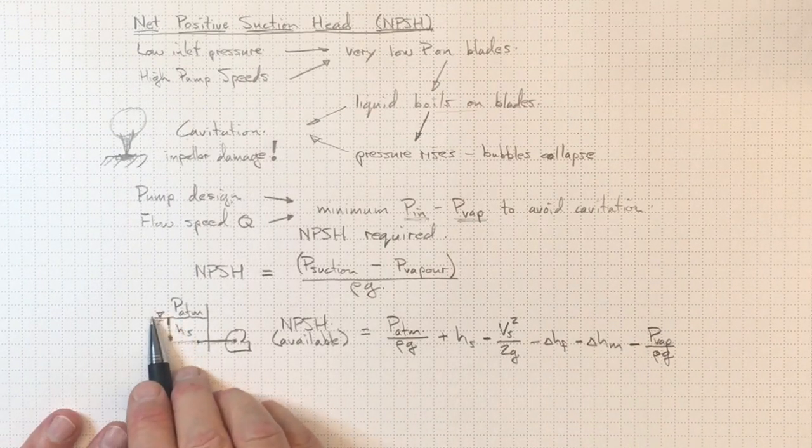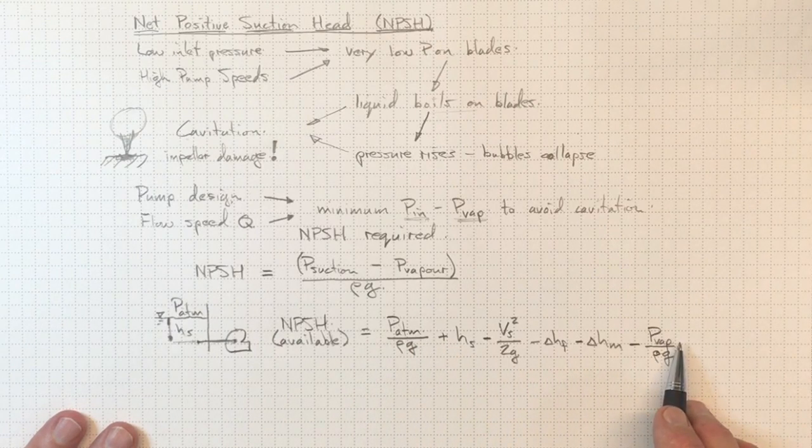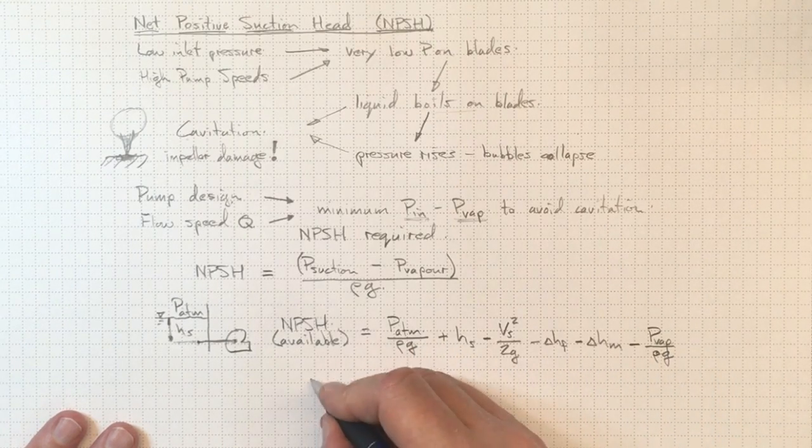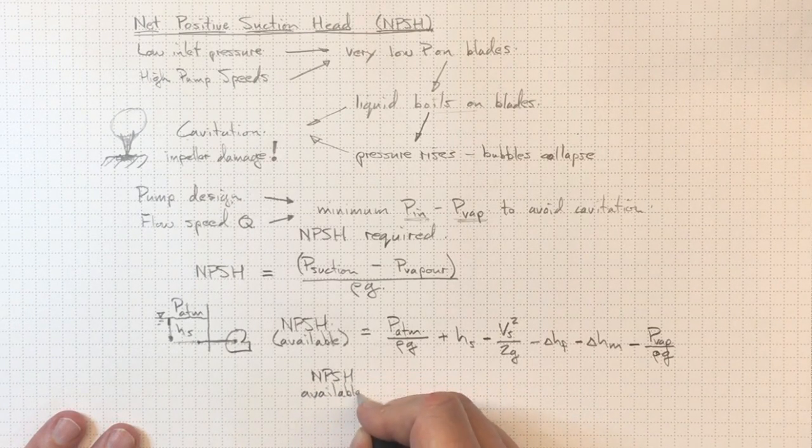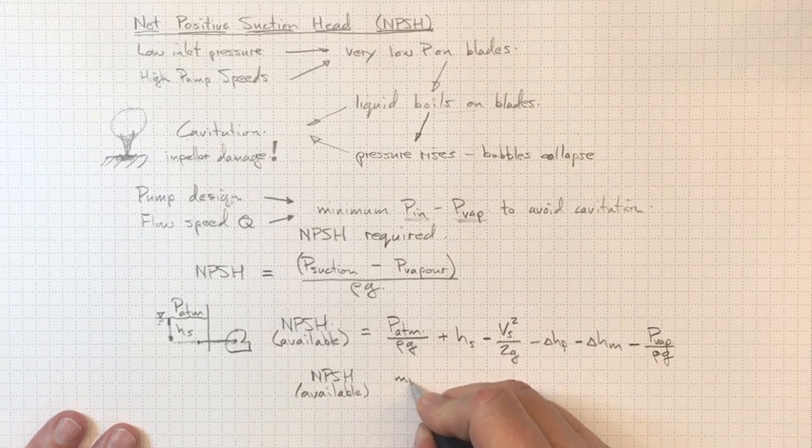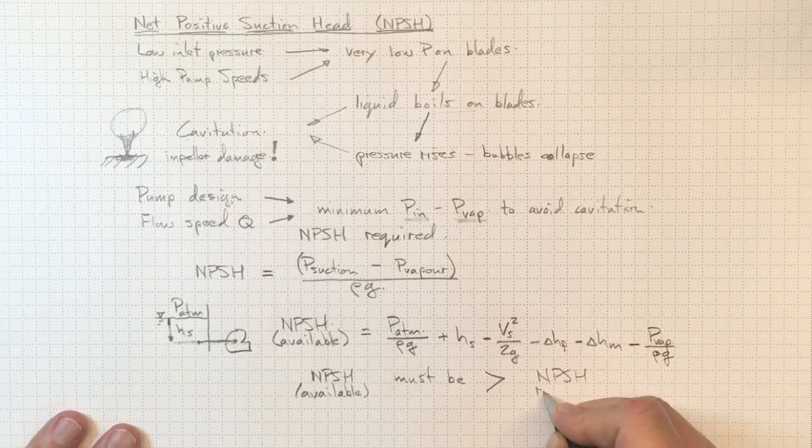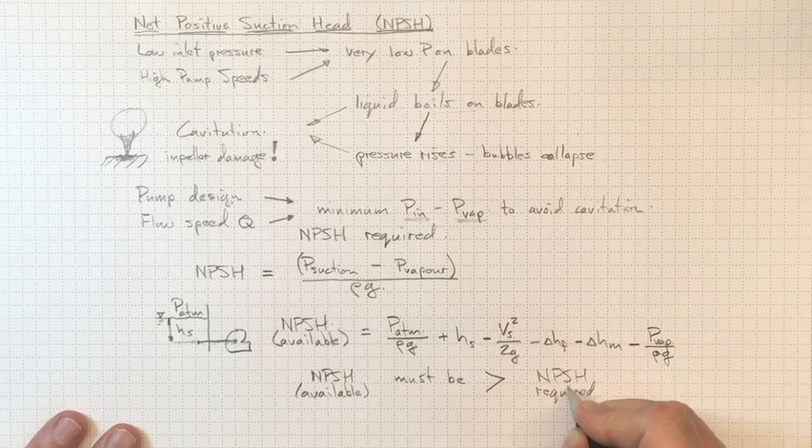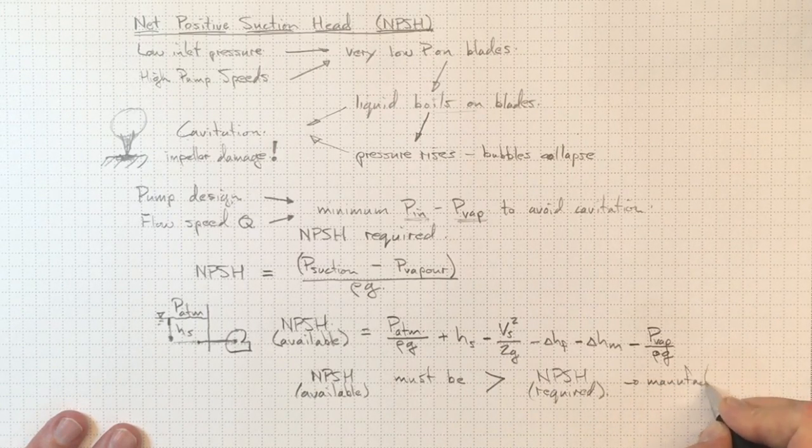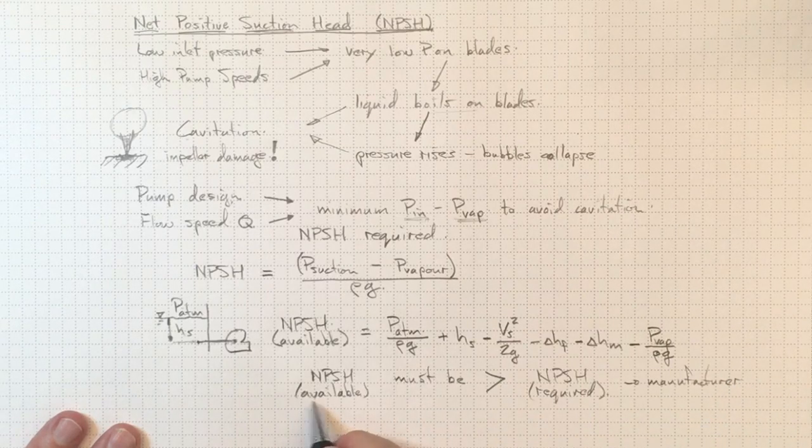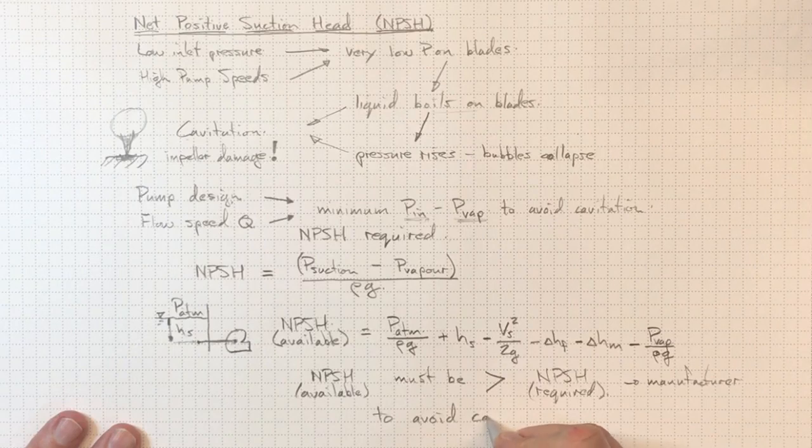So if we've done our piping design, we should be able to figure out what all of these things are in order to figure out how much NPSH we've got available. And then the test is simple. We just need to make sure that the NPSH available must be greater than the NPSH required that we got from the manufacturer. If we take care to make sure that that relationship is met, then we will avoid cavitation.